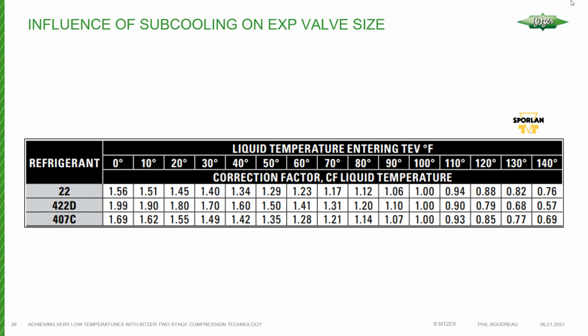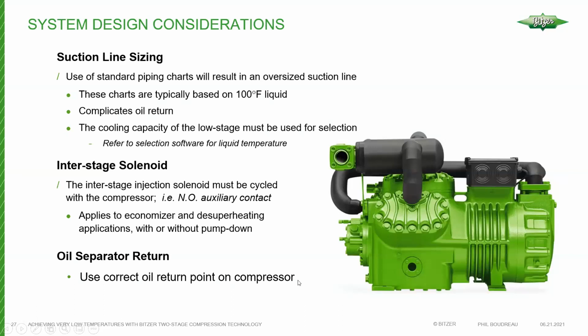This is a small table that I pulled from a Sporlan catalog at one point. If you take a look at the 100 degrees Fahrenheit column, you'll see that the factor is 1, which means the nominal size of the valve is whatever the tonnage rating is, multiplied by 1. But as the temperatures drop, for example at 30 degrees Fahrenheit, we'll just pick R407C there at the bottom, not a common one actually for low temp, but I just put it here as an example. At 30 degrees Fahrenheit, we can see that the increase in capacity of that valve is 49%. So if you're already oversized by 20%, now you're going to be oversized by this much more capacity. And in the case of 422D, it's 70%. So I just put this up here to show you the impact of subcooling. We want to be very careful with that.